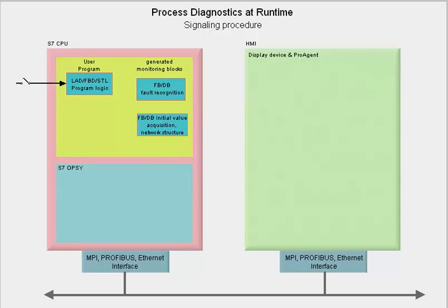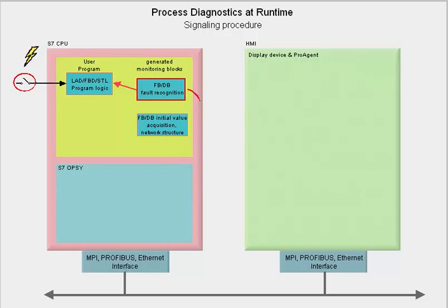Let us now assume that one of the sensor signals takes on a fault status. As soon as the result of logic operation shows a deviation from the set point state, the fault recognition mechanism stores all the signals belonging to the operation in an initial value acquisition. This information and the stored network structure are important for later criteria analysis.